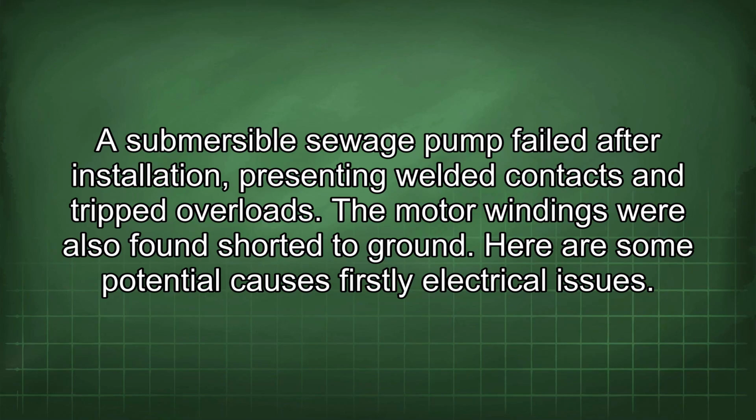A submersible sewage pump failed after installation, presenting welded contacts and tripped overloads. The motor windings were also found shorted to ground. Here are some potential causes.